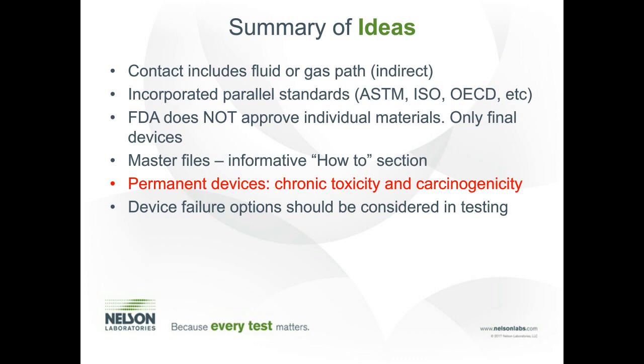They are a good way to evaluate systemic toxicity and carcinogenicity along with genotoxicity without having to do these types of tests. The reason why these tests are not normally done is that the carcinogenicity tests, especially, are very expensive and long tests. So we really want to try to evaluate those through materials and, more importantly, chemical characterization with their appropriate toxicological evaluation rather than actually performing those endpoints. It will save you a lot of time and headache.